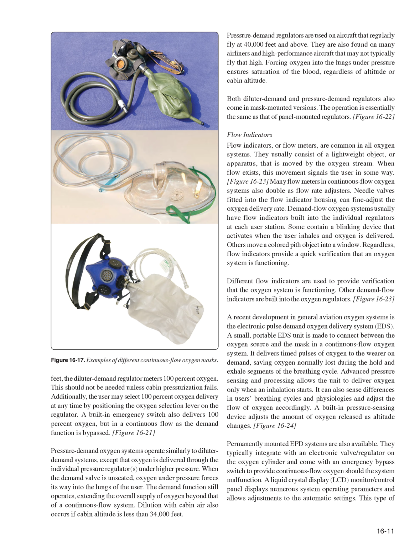Figure 16-24: permanently mounted EPD systems are also available. They typically integrate with an electronic valve/regulator on the oxygen cylinder and come with an emergency bypass switch to provide continuous flow oxygen should the system malfunction. A liquid crystal display, LCD, monitor/control panel displays numerous system operating parameters and allows adjustments to the automatic settings.